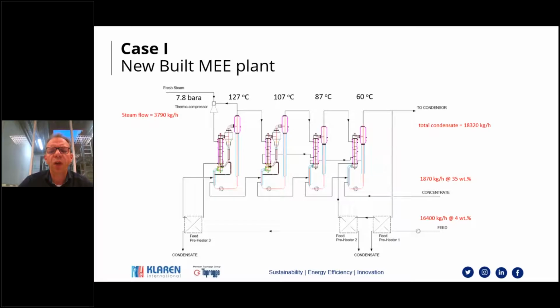One other thing we have done to improve the steam economy is to use condensate flashing from the second to the third effect, and from the third effect to the fourth effect. Based on the pressure difference, you have some flashing of this condensate stream in the shell side, releasing heat and improving the energy efficiency.